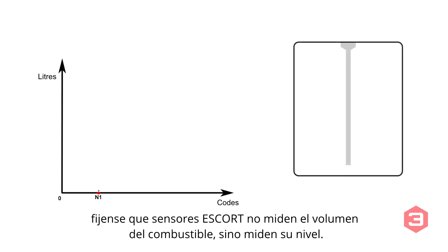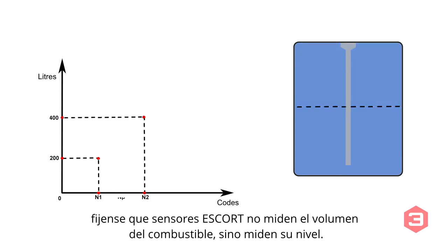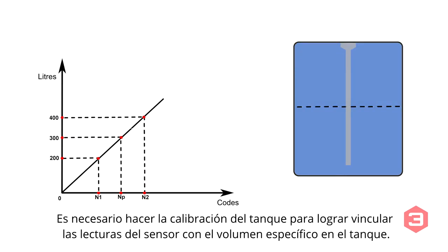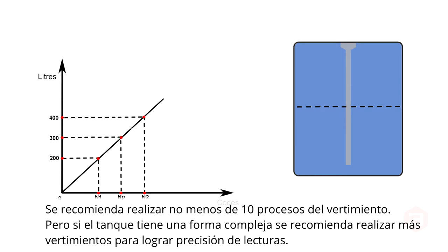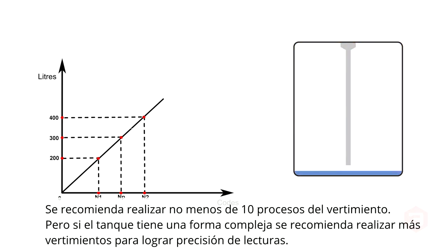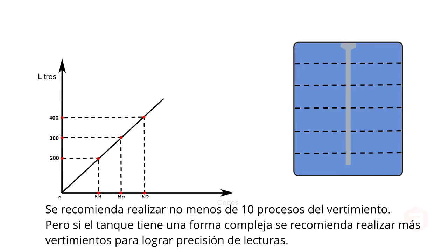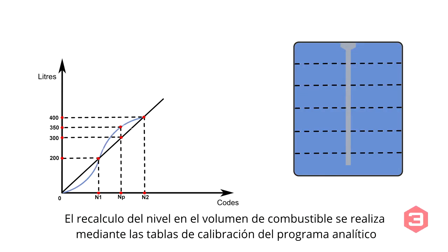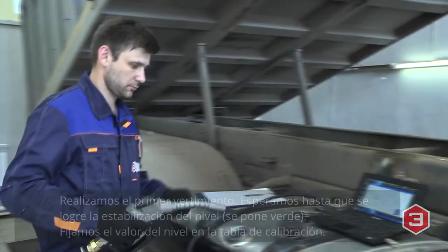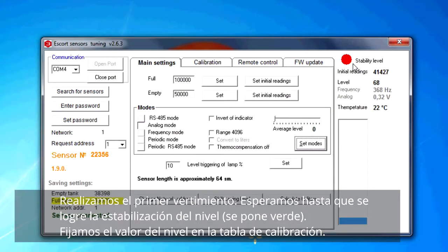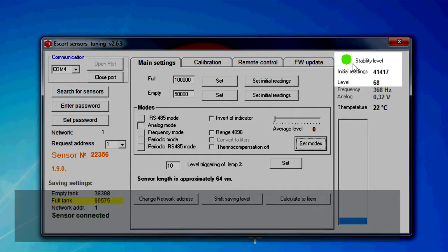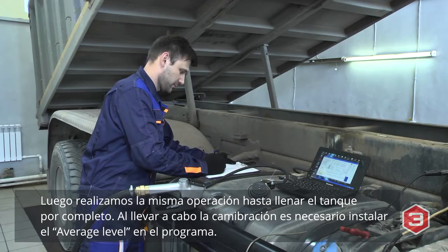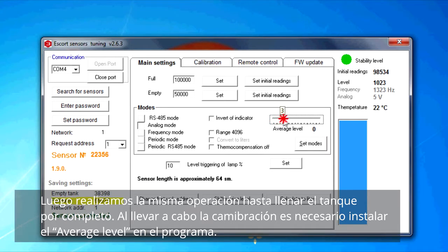Calibration. It should be noted that Escort TD sensors measure the fuel level, not volume. In order to link sensor level with specific volume, calibration is needed. We recommend to perform this procedure at least 10 times, but more measurements may be needed for accurate readings for tanks with complex shapes. Fuel level to volume conversion is performed using calibration tables in analytical software. Fill the first portion of fuel. Wait until the fuel level stabilizes. Fill in the level reading to the calibration table. Repeat for each portion till full tank. Enable smoothing when calibration is finished.